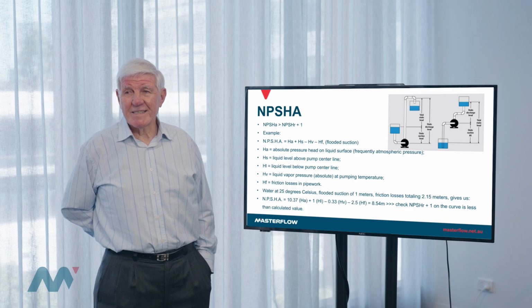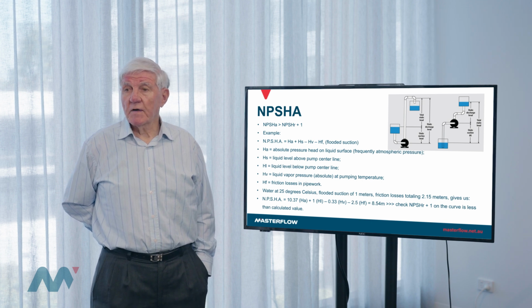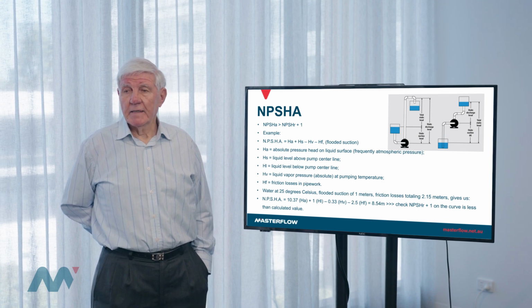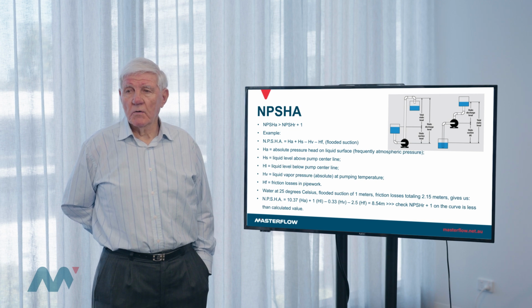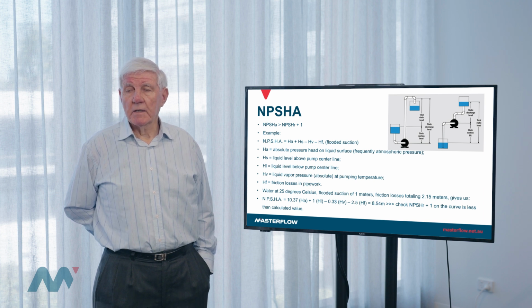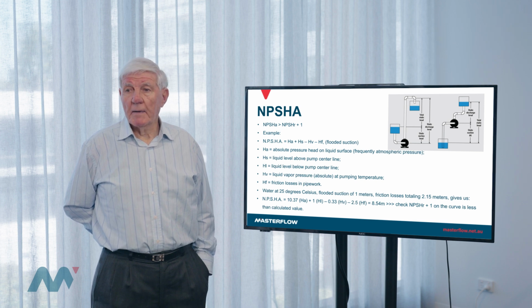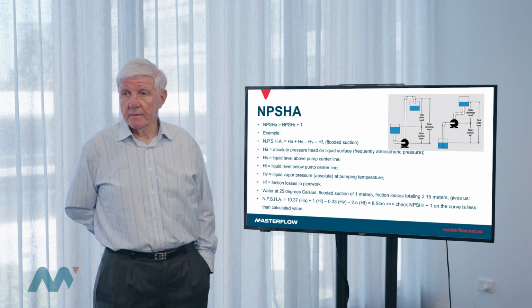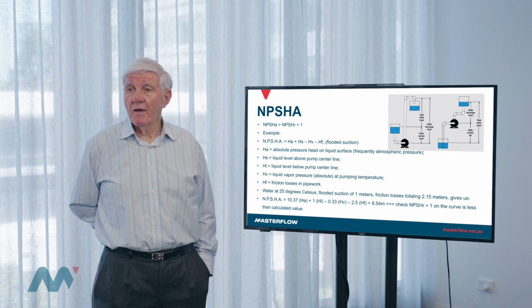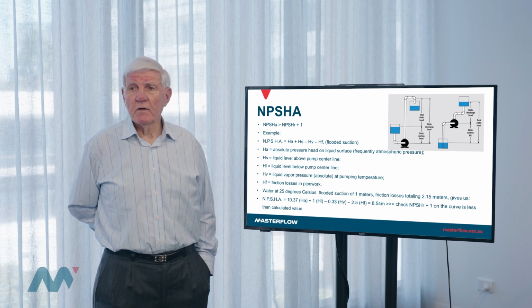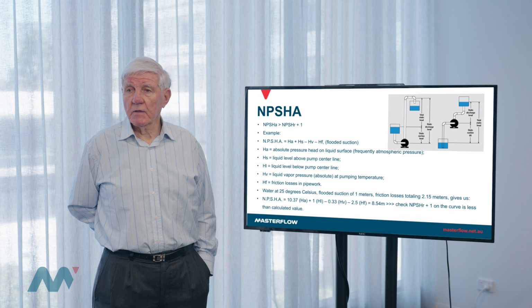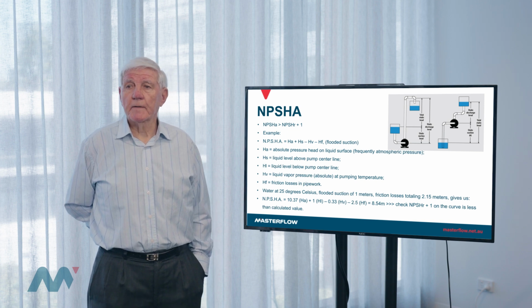NPSH actually consists of two components. The first is NPSHA, which is a function of the system. And it represents the pressure that's on the suction eye of the impeller as a result of the system head, less the losses in the suction pipework. And that will come up to a certain value, which you can calculate. And you should make that calculation for every system. There's no universal NPSHA. You have to calculate it for your individual system.